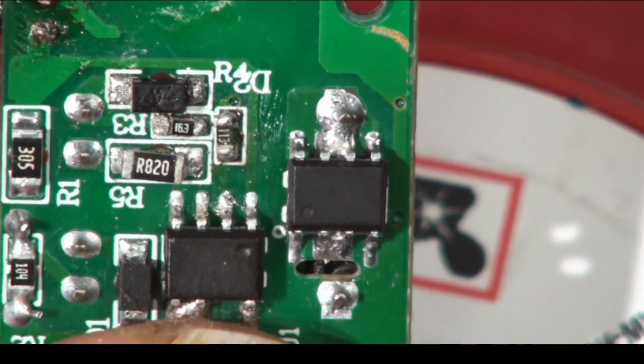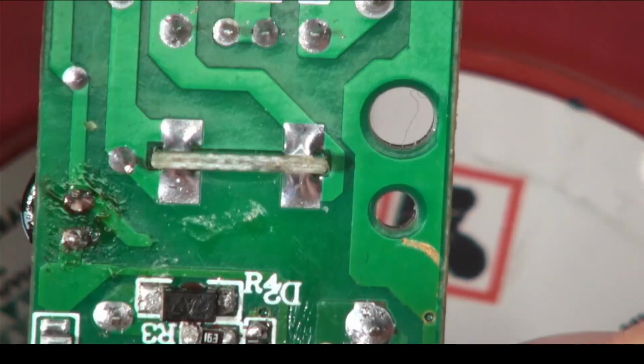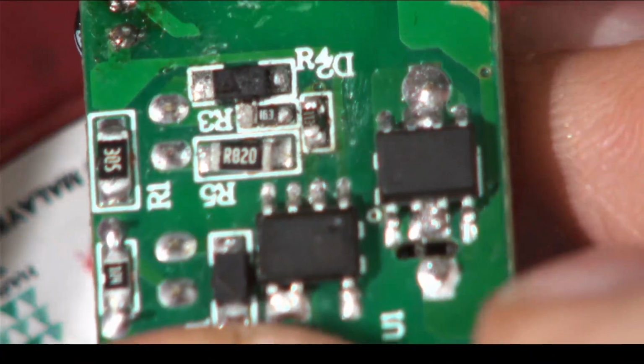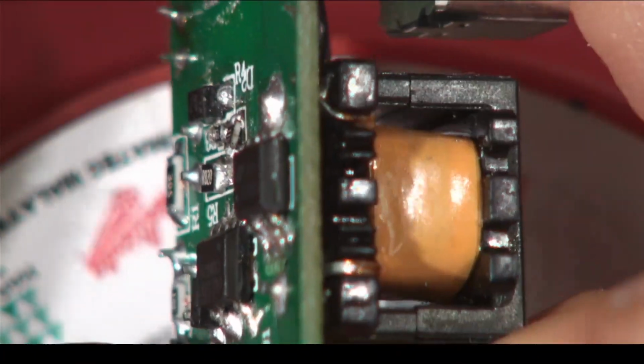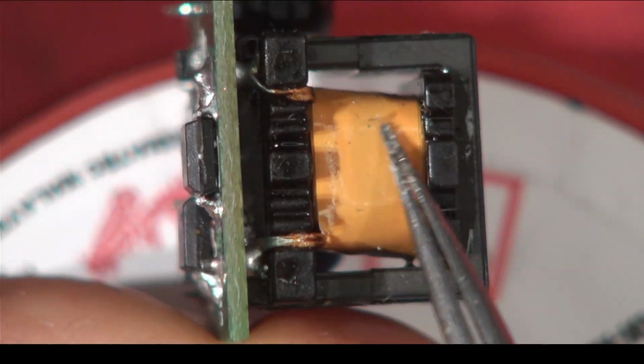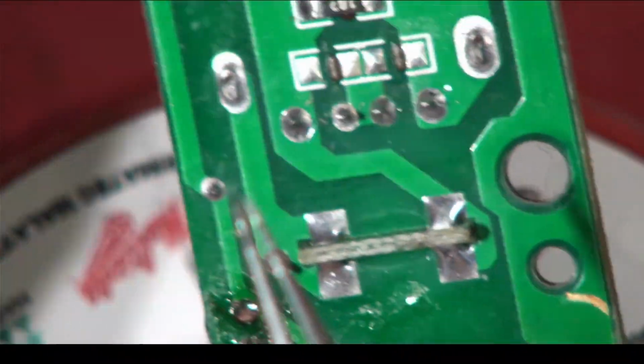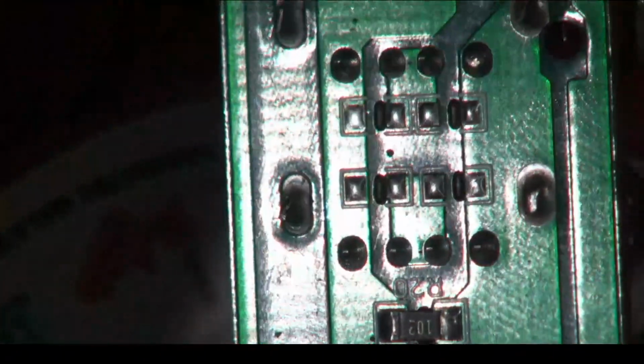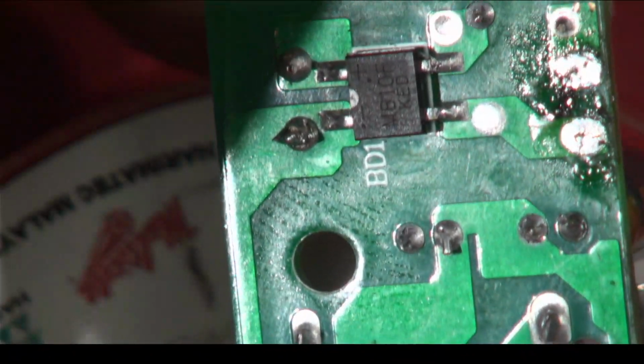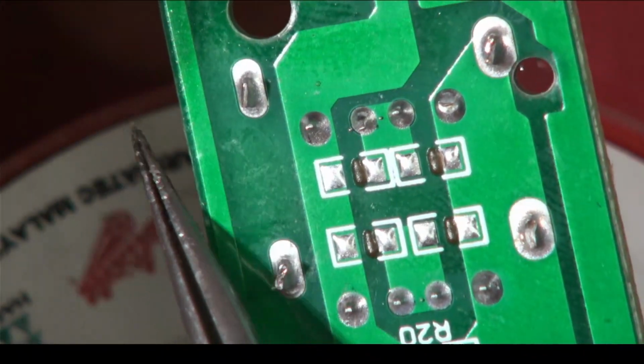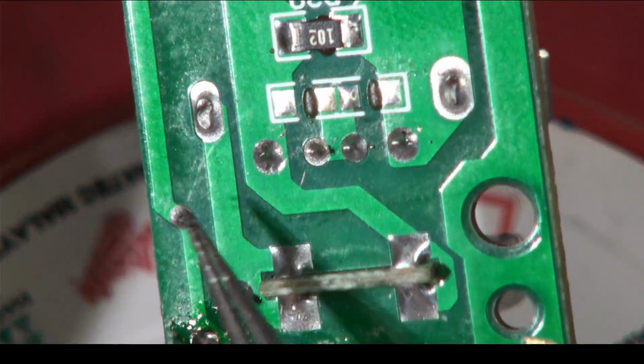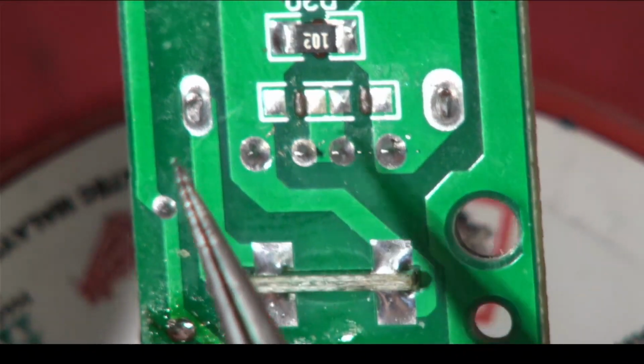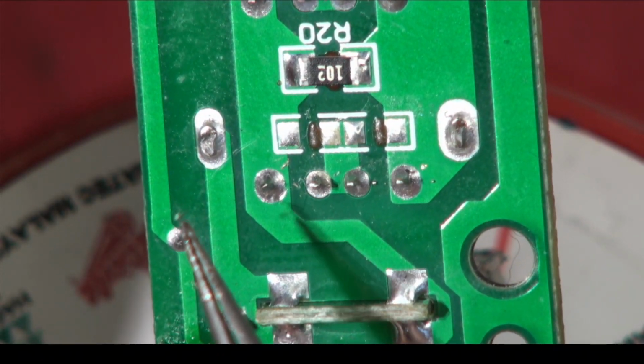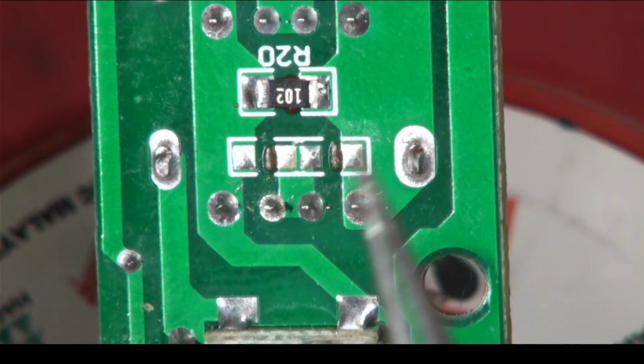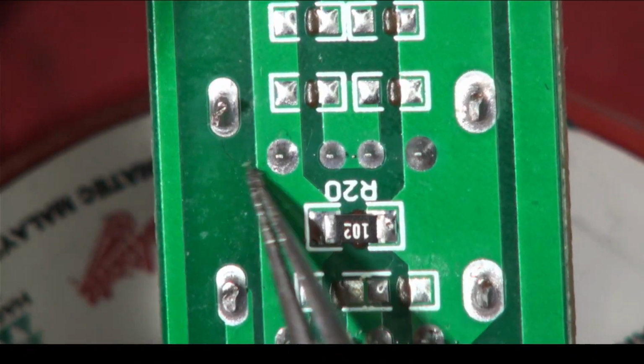There is some capacitive coupling, which we can talk about another time, but the significant one is the magnetic coupling. So unless the insulation breaks down or you get some kind of short or condensation, you should be relatively safe - although this isn't really adequate separation, especially for the high to low side, the AC high voltage side and the DC low voltage safe side. This isn't really adequate.